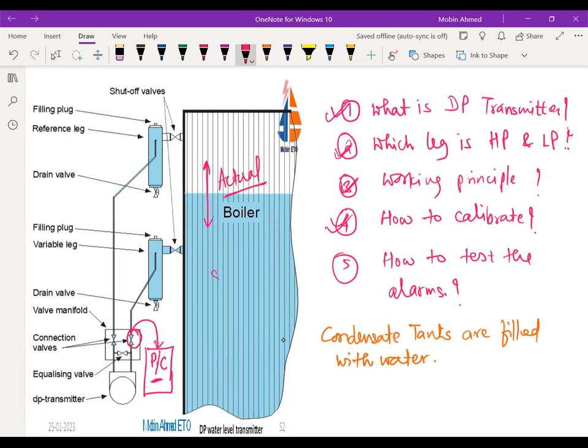So start the pump, that is the feed water pump, in manual mode, and let it be filled. So from here it is going to rise, but you need to be very cautious here. There is going to be a problem with the thermal stress, so you cannot fill the cold water. Cold water means hot well water, that is at 95 degrees centigrade, and the boiler water is almost 200 degrees centigrade. Almost this water temperature is going to be 150 near about. So this 95 degrees centigrade becomes a cold water for this boiler drum.